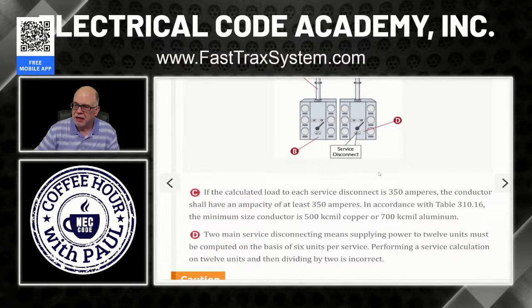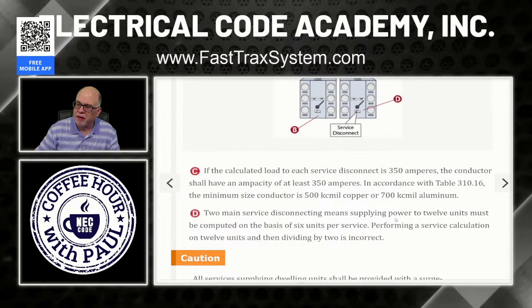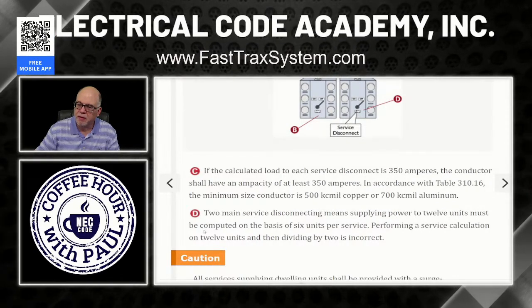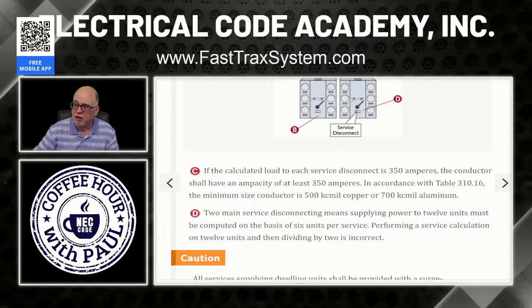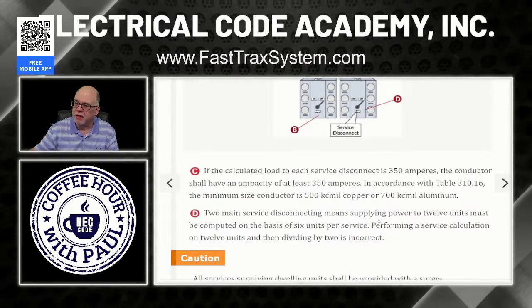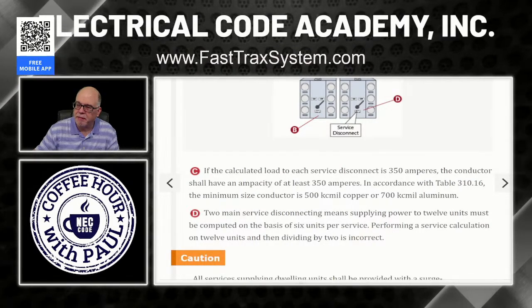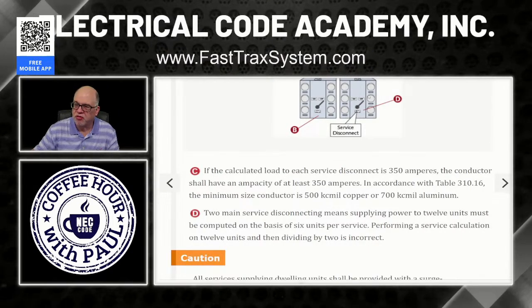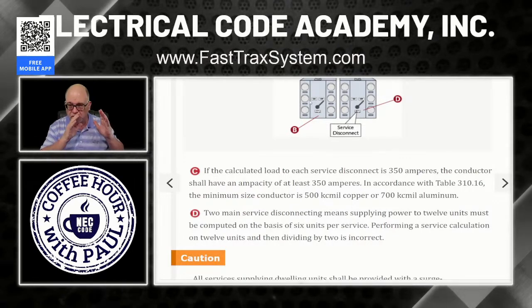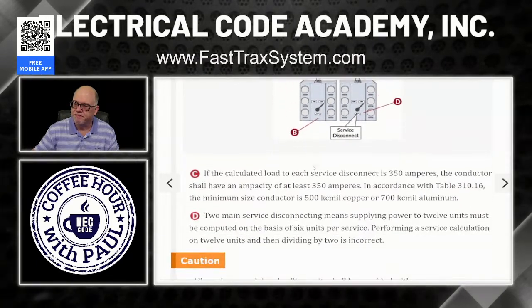That's not a problem. D, right here, says two main service disconnecting means supplying power to 12 units must be computed on the basis of 6 units per service, right? Obviously, this is 6 here, this is 6 over here, okay? And it's a 12-unit total complex, right? We got that. Performing a service calculation on 12 units and then dividing that by 2 is simply incorrect, okay? So you're going to do the calculation based on 6 at a time because they're separated out. So you're doing 6, and then you're doing the calculation for 6 over here for these conductor sizing, all right?